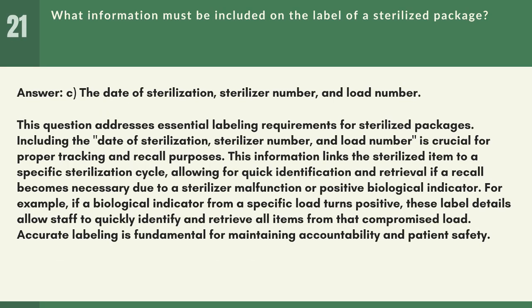Answer: C. The date of sterilization, sterilizer number, and load number. This question addresses essential labeling requirements for sterilized packages. Including the date of sterilization, sterilizer number, and load number is crucial for proper tracking and recall purposes. This information links the sterilized item to a specific sterilization cycle, allowing for quick identification and retrieval if a recall becomes necessary due to a sterilizer malfunction or positive biological indicator.